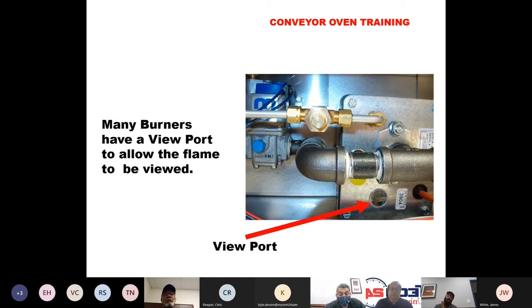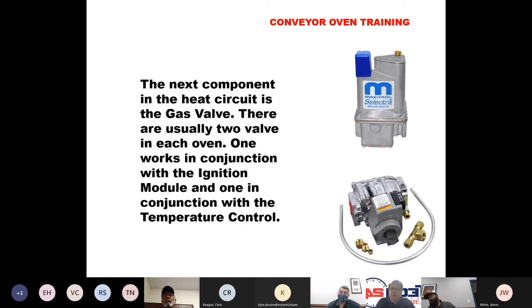A lot of burners will have a little viewport. That viewport is only going to tell you that you can see a flame. It's not going to give you much of an indication of the quality of it. Flame current is really the only measurement of the quality of flame on a burner like this.